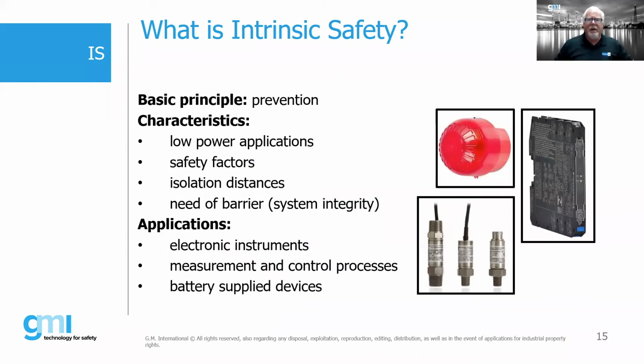So what is intrinsic safety? Again, it's a prevention. The characteristic is that it's a low power application. There have been many cases, and we've had questions in the past, where people say, I'd really like to make a motor starter intrinsically safe or a light fitting intrinsically safe. And I've seen that in some specifications where clients are calling out, I want intrinsically safe lighting. Intrinsic safety is a low power, low energy type application. What we're trying to do is make sure that any arcing or sparking that's taking place is below the minimum ignition energy of the flammable gases and vapors which could be present. So we're typically talking about 1 watt of power or less. So it's generally limited to instrumentation circuits, very low power, 4 to 20 milliamp type circuits.